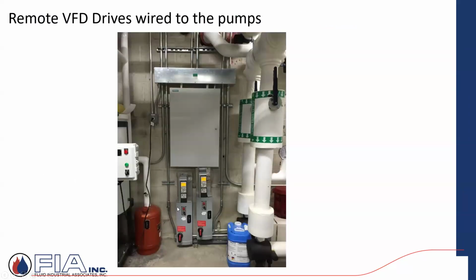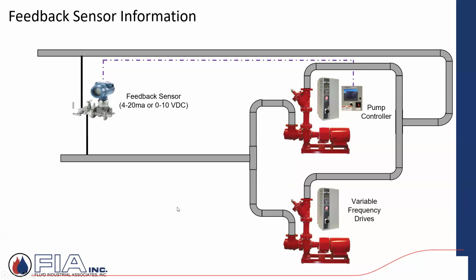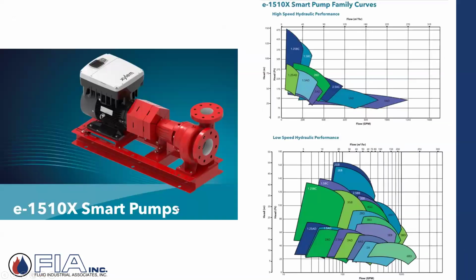Sometimes those drives aren't going to be pump mounted. In fact, a lot of times when you get into the bigger pumps, they are located remote, relatively speaking, up on a wall, perhaps. So the drives are right there, near the pump, but up on a wall, and then the DP sensors are remote out in the system.